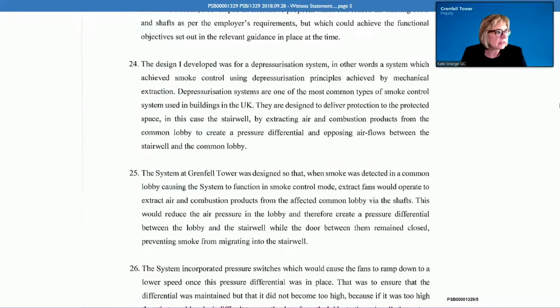I see. And then he says in paragraph 25, the system at Grenfell Tower was designed so that when smoke was detected in a common lobby, causing the system to function in smoke control mode, extract fans would operate to extract air and combustion products from the affected common lobby via the shafts. This would reduce the air pressure in the lobby and therefore create a pressure differential between the lobby and the stairwell, while the door between them remained closed, preventing smoke from migrating into the stairwell.